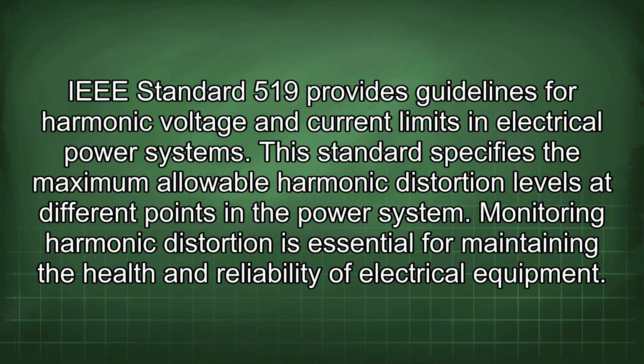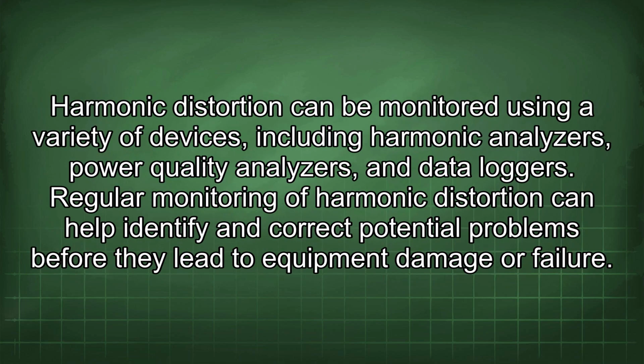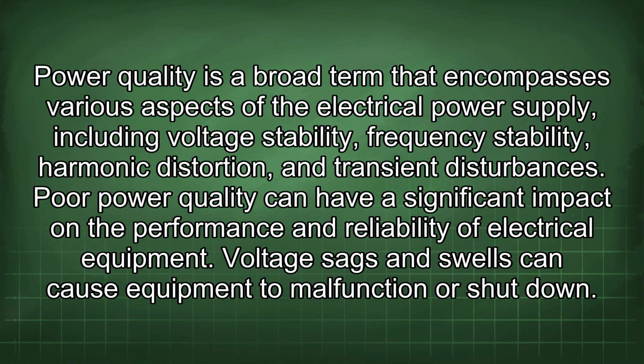Monitoring harmonic distortion is essential for maintaining the health and reliability of electrical equipment. Harmonic distortion can be monitored using a variety of devices, including harmonic analyzers, power quality analyzers, and data loggers. Regular monitoring of harmonic distortion can help identify and correct potential problems before they lead to equipment damage or failure. Power quality is a broad term that encompasses various aspects of the electrical power supply, including voltage stability, frequency stability, harmonic distortion, and transient disturbances. Poor power quality can have a significant impact on the performance and reliability of electrical equipment.